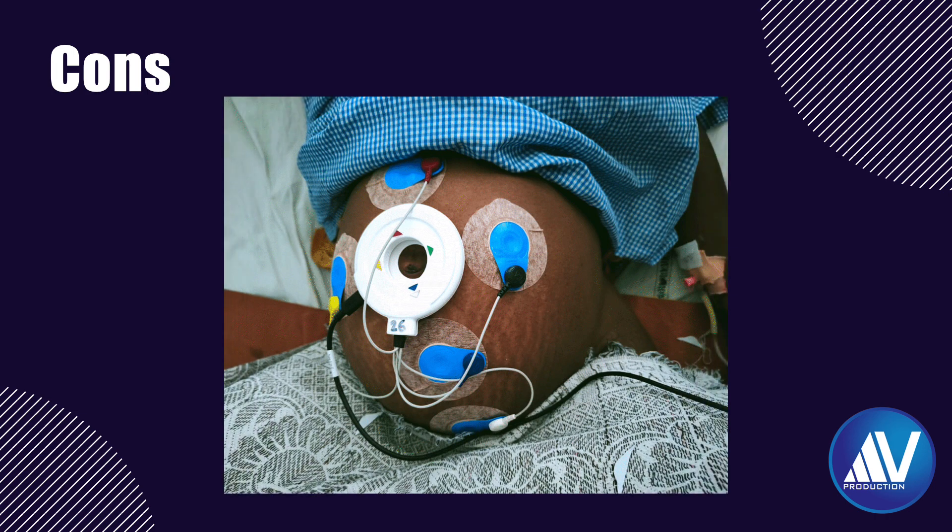The drawbacks of this technology are: application of electrodes on the abdomen is very elaborate, if not a tedious process. The signal and therefore the graph on the tablet gets interrupted when the patient moves around in the labor ward, although this has been fixed in the later version. As yet, the Dakshya app is only available for Android phones and not for iPhones, though they will soon release an iPhone-compatible version.